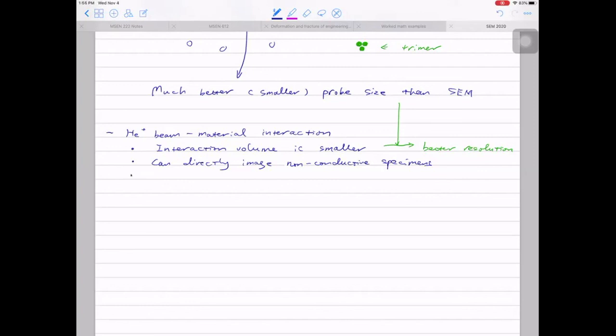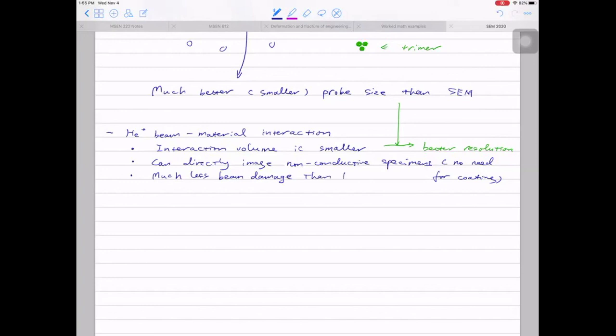Comparing helium ion microscopy with focused ion beam: for HIM we use helium, and for FIB we use gallium. Gallium is much heavier and larger than helium, so the beam damage in helium ion microscopy is much smaller — much less beam damage than FIB, which uses the gallium source.